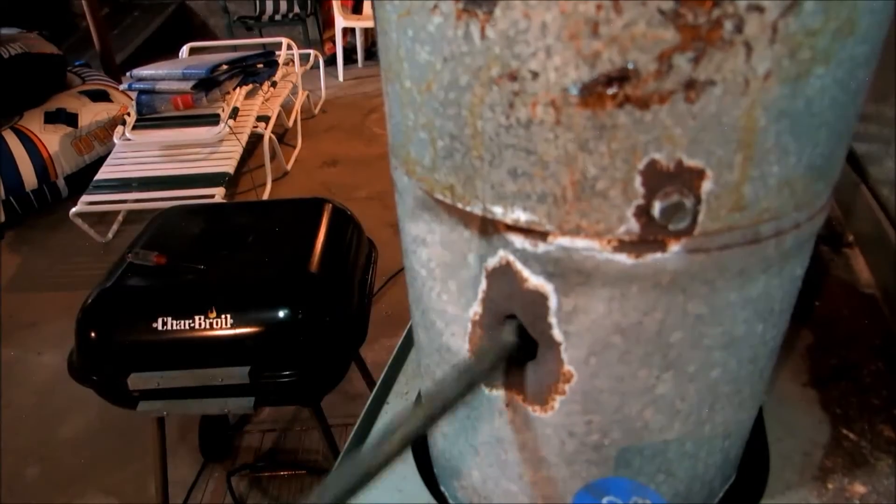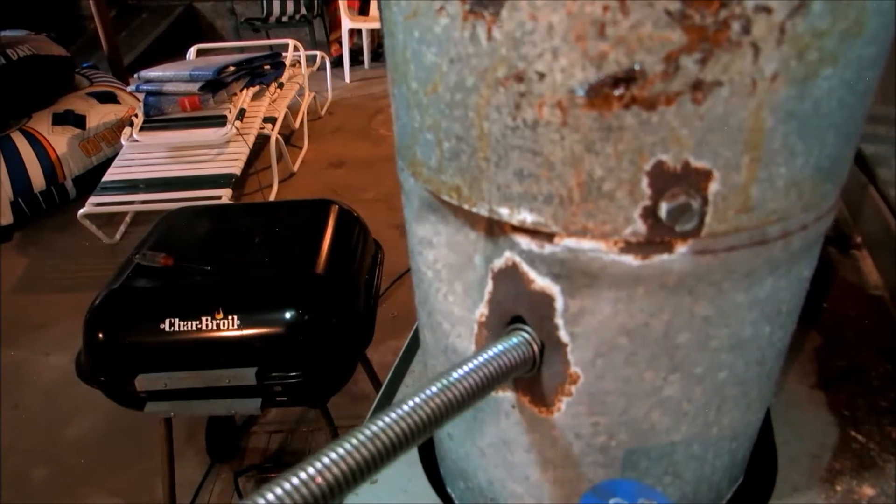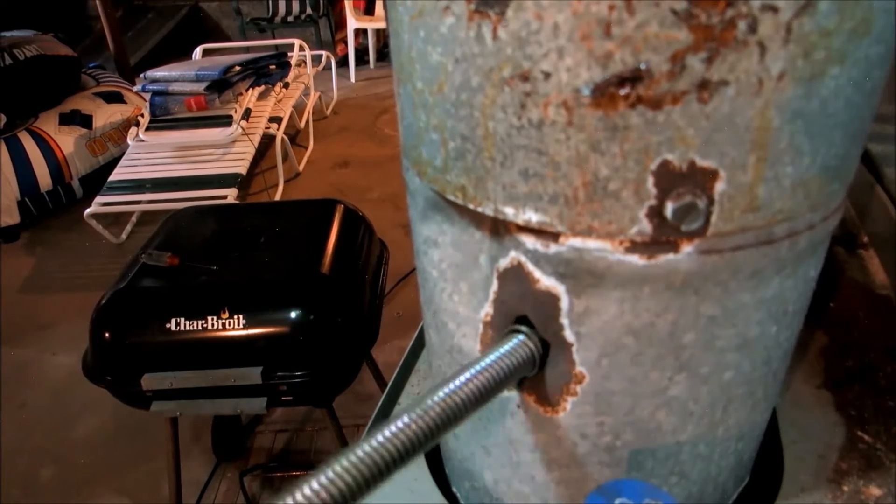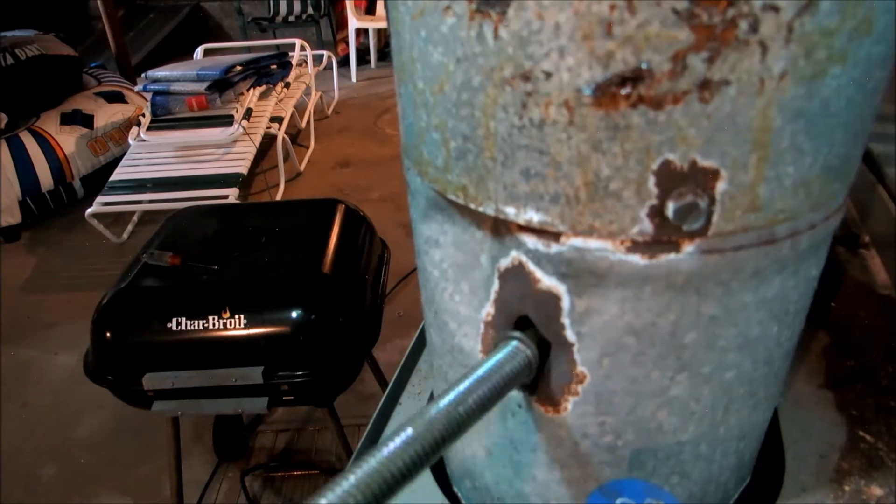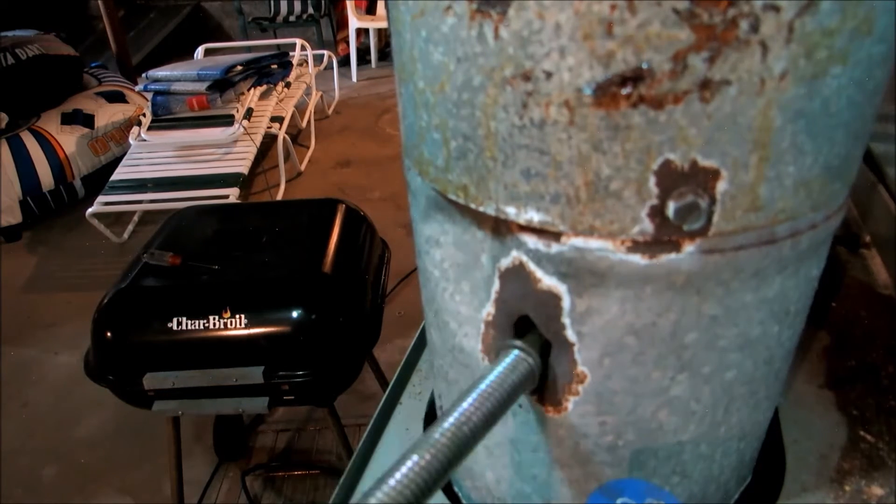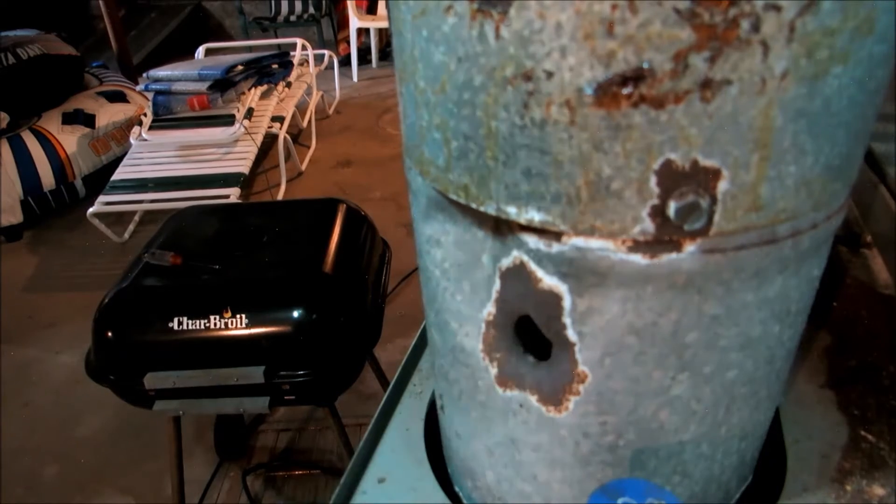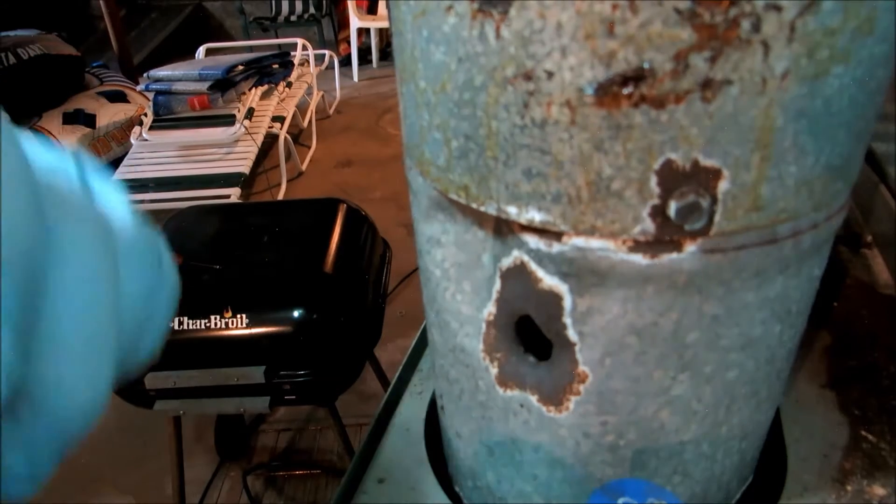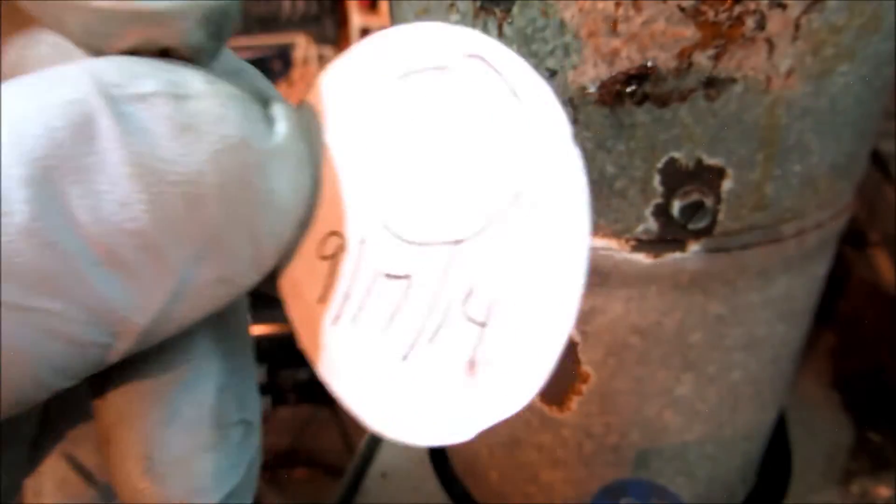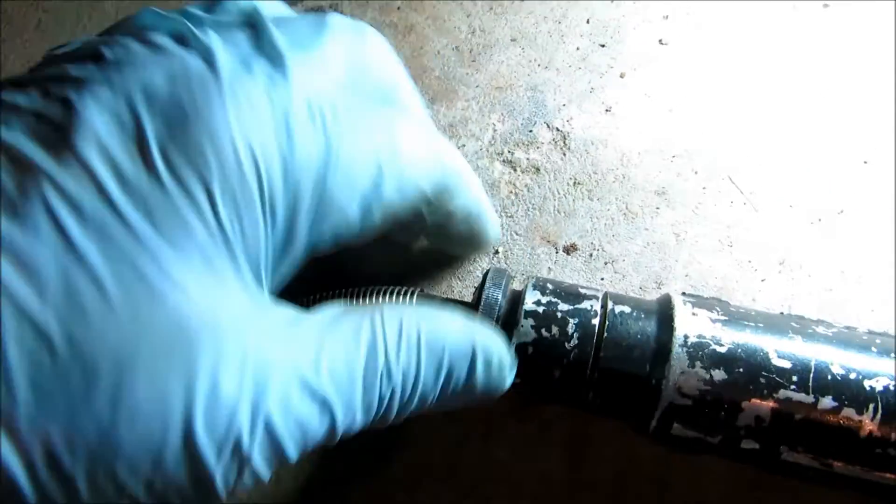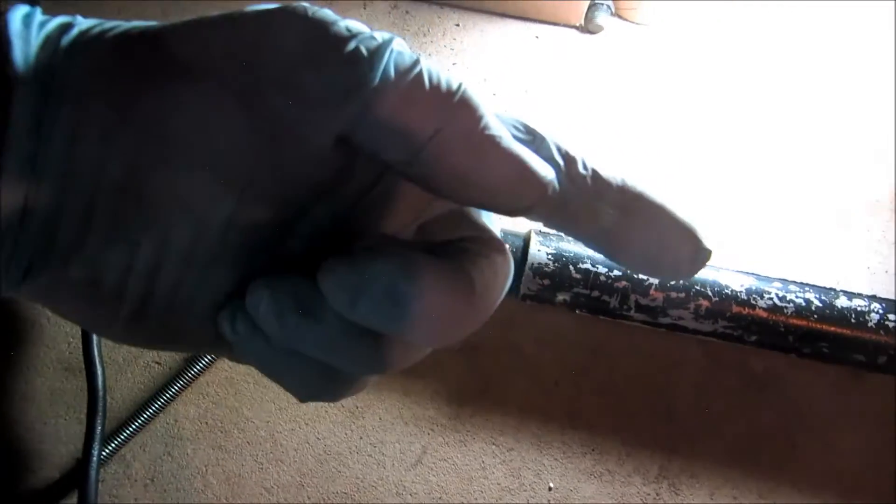We're on a smoke test. It's just a little paper that goes in there like that. I'm going to stick it in there and pump it ten times. See? If it was black it'd show right up on that little dot right there. I'll circle it for you. See it? That's clear, zero smoke. This is a little pump. There's a little end here that unscrews. You stick the paper in there and tighten up this end - that holds the paper in there. You just pump it, stick that in the smoke pipe. You pump this ten times. It pulls the air that's inside the smoke pipe through the paper, so if it's black it'll show up on the paper. Smoke test, very simple.